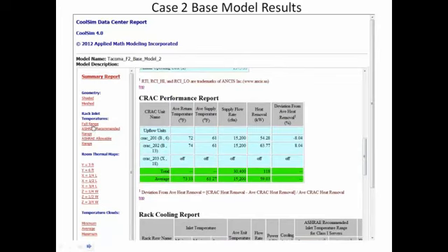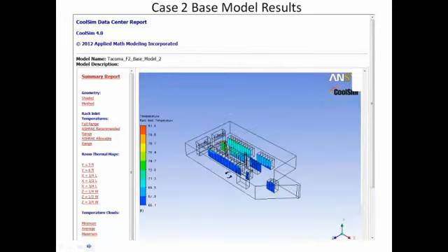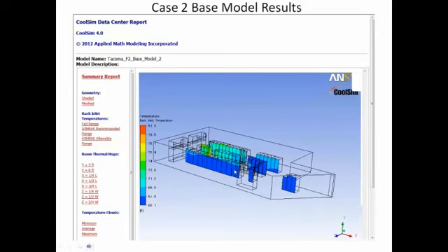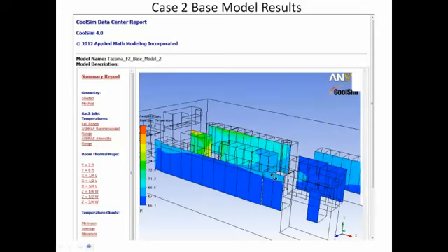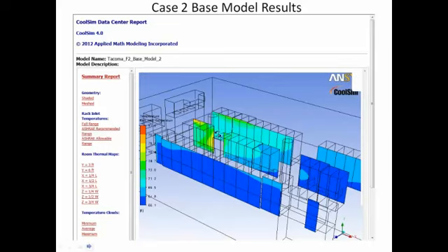So if we take a look at the full range of temperature here, you can see the problem that is going to be the case in this design. These racks over here near the cooling unit aren't getting much cold air. You see their temperatures are higher. This is a full distribution of temperature, so the low on the rack inlets is 66 degrees. The high is 81 degrees. And you see the highest temperatures sensed on these rack inlets are the ones closest to the CRAC units.